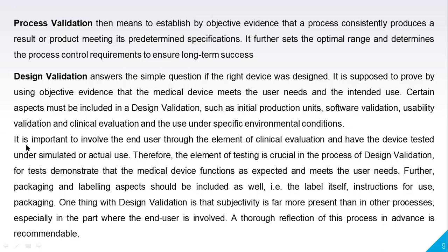Right? So it is important to involve the end user through the element of clinical evaluation and have the device tested under simulated or actual use. Therefore, the element of testing is crucial in the process of design validation. The tests demonstrate that the medical device functions as expected and meets the user needs.